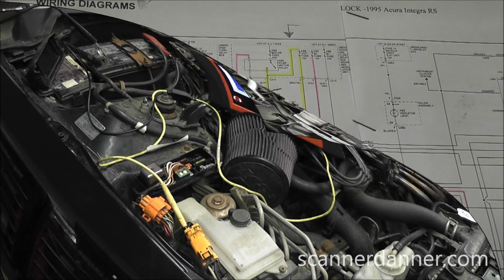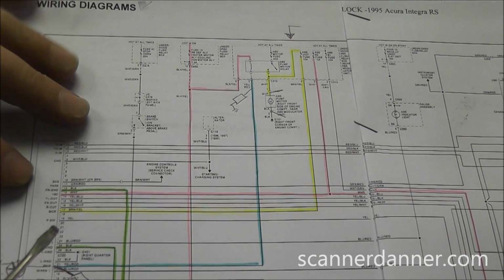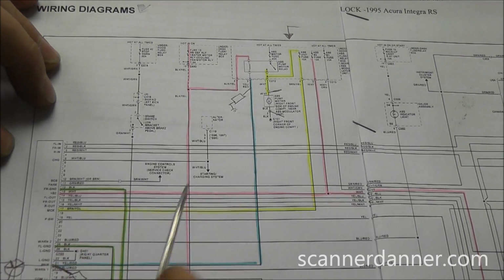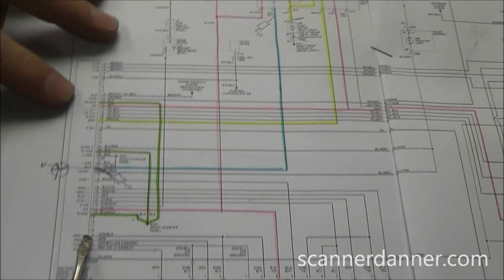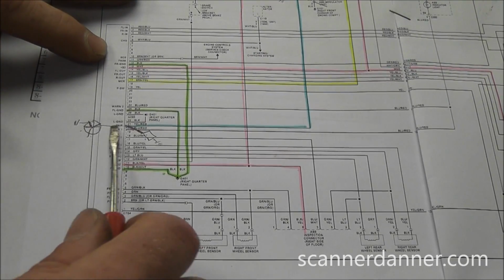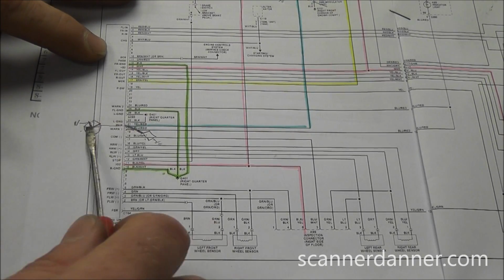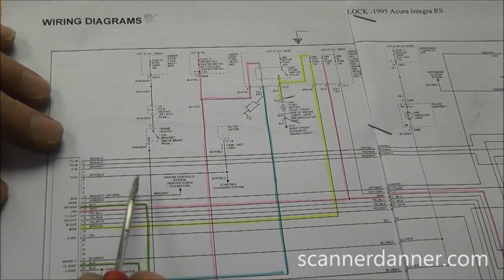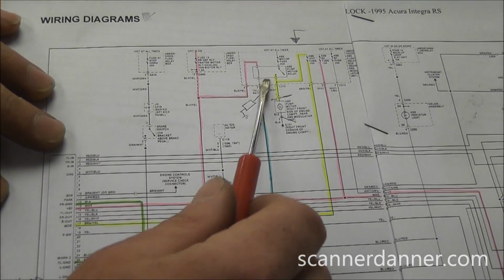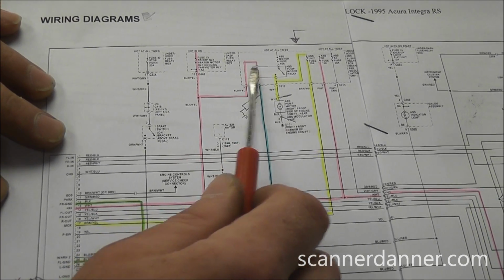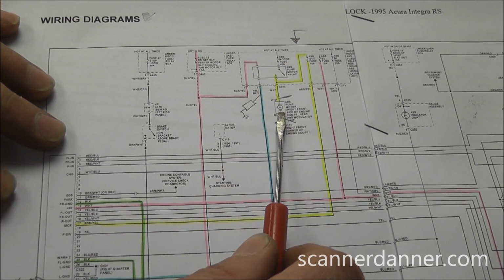Let's go back to the wiring diagram. Okay, let's see if you guys can follow this. The computer controls the pump relay on this blue line right here. We give this a ground - that's going to energize the relay, makes a coil, a magnetic field, pulls the switch closed, runs the pump.